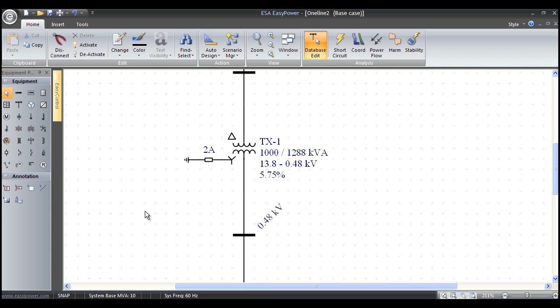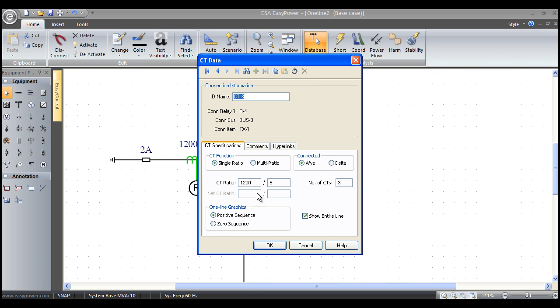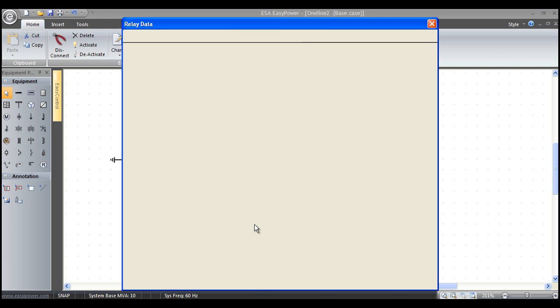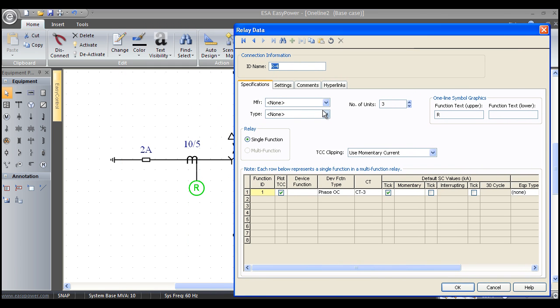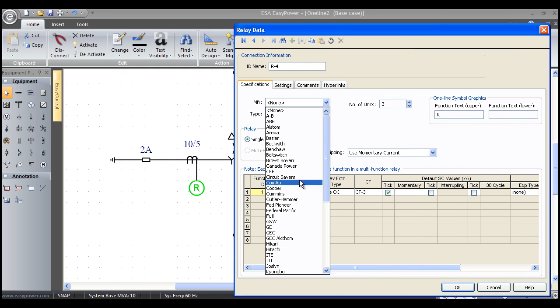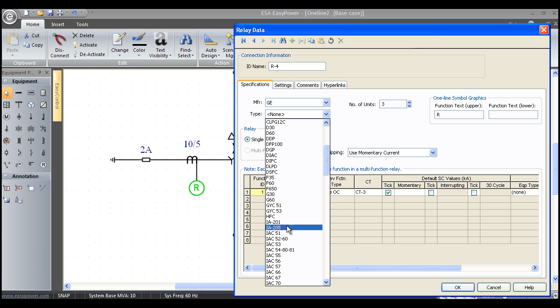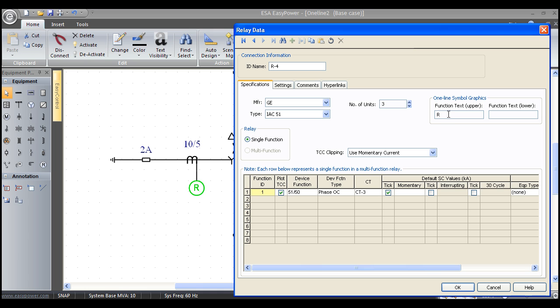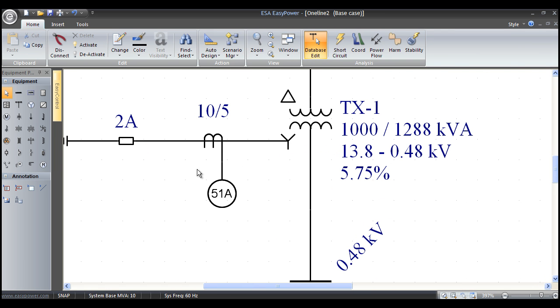When I say OK, now here's our transformer. I can actually grab a CT and a relay and so now we can make a high resistance grounding alarm system. I can double-click on this CT, make it a 10 to 5 unit, 1 CT. We'll double-click on this relay and we'll pick a General Electric old IAC 51 unit, and this will be one unit and it will be a 51 alarm. When I say OK, now I've got my high resistance grounding system for this transformer.